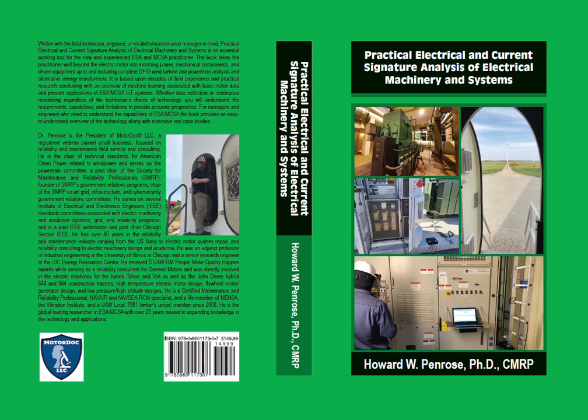My first application surrounding the use of ESA was in 1994, troubleshooting an electric motor at a petrochemical facility in northern Illinois on a Sunday. I had experience from the U.S. Navy in the mid-1980s and had just completed additional training in vibration analysis. The customer had a problem with loading a 4,160-volt compressor motor, as it would trip on overcurrent.